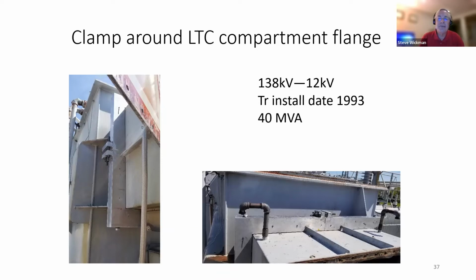The only records I had were that this transformer was installed in 1993, and this repair was done about 2 years ago. And I would imagine this transformer was new when it was put in place in 1993. So it gives you an idea of the life of the transformer, and the fact that that gasket is probably at the point where it's time to deal with it and address the leaking.